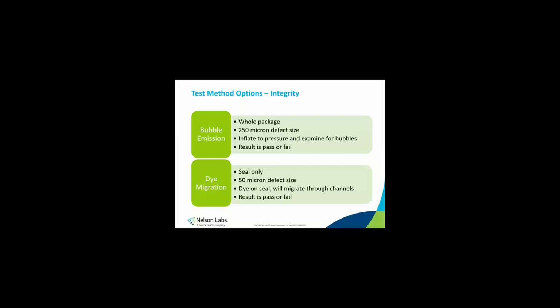For a bubble test, the whole package is tested, and the method can reliably detect a 250 micron defect. The test is run by inflating the package underwater to a set pressure and looking for air escaping as bubbles. For the dye test, only the seals are tested, and this method can reliably detect a 50 micron defect. The test is run by placing the dye on the seal and visually looking for it to pass through a channel. Let's look at the bubble video.